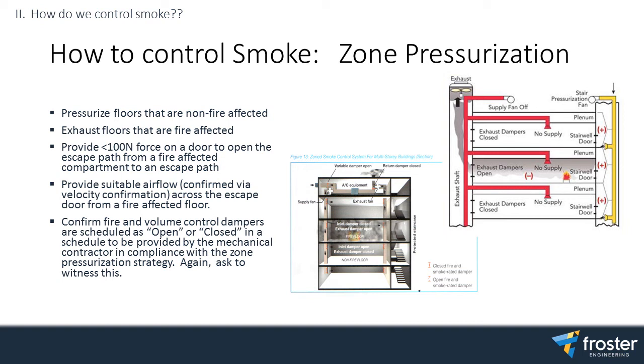If you have a fire-affected floor, you want to extract it. You have dampers set up so that you close off your air handling system feeding that floor, shut down. You extract it out completely, and then you maintain pressurization on the non-affected floors. You refer to it as sandwich pressurization, which is what Stephen and I have done on 8 Davidson Terrace.